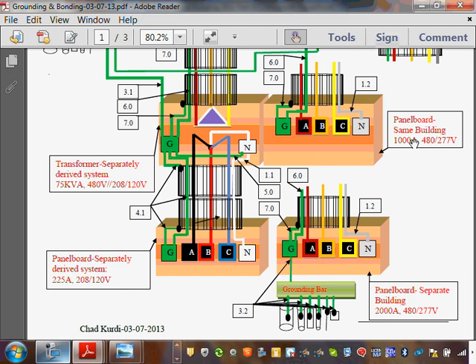Okay, now you're going to make me put my engineering hat on. When we have, guys, a campus, a good engineered project campus, you will have one solid grounding electrode system together. All these buildings will be in close proximity to each other, and they will engineer it so they are all tied together. The grounding electrode system will be tied all together. That's the best way to do it. But do you have to if they're completely separate from each other? You don't have to. Would it be a good idea if you have a campus that every building has a grounding electrode system and all the buildings in that campus are bonded together? Absolutely. With 1-aught or 4-aught like we do? Absolutely. So, okay, that's your grounding and bonding at the second building.